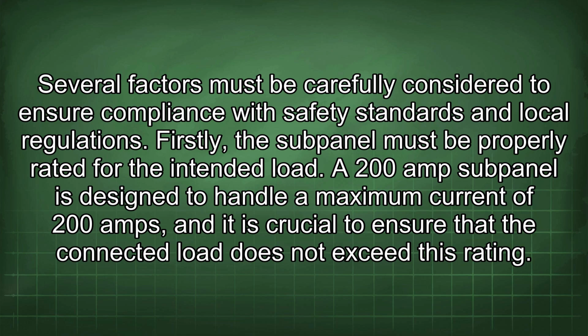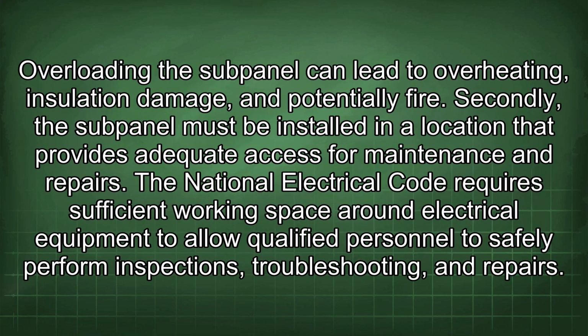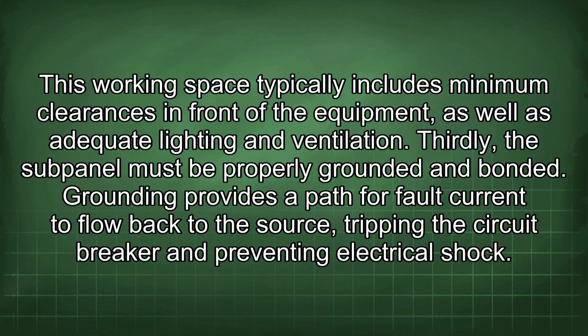Firstly, the subpanel must be properly rated for the intended load. A 200 amp subpanel is designed to handle a maximum current of 200 amps, and it is crucial to ensure that the connected load does not exceed this rating. Overloading the subpanel can lead to overheating, insulation damage, and potentially fire. Secondly, the subpanel must be installed in a location that provides adequate access for maintenance and repairs. The National Electrical Code requires sufficient working space around electrical equipment to allow qualified personnel to safely perform inspections, troubleshooting, and repairs. This working space typically includes minimum clearances in front of the equipment, as well as adequate lighting and ventilation.